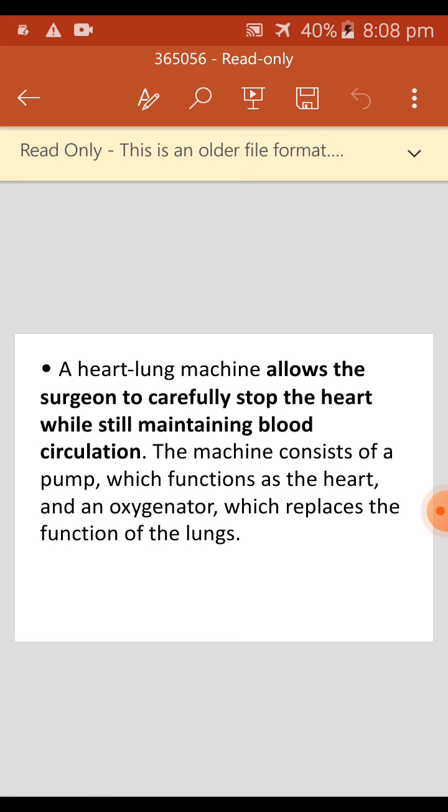Structure and function of the heart-lung machine. The HLM is the basis of ECC and covers two important organ functions. One is the pump function of the heart, another one is the gas exchange function of the lungs. It must ensure a sufficient perfusion volume that corresponds to the normal cardiac output of the patient under anesthetic.